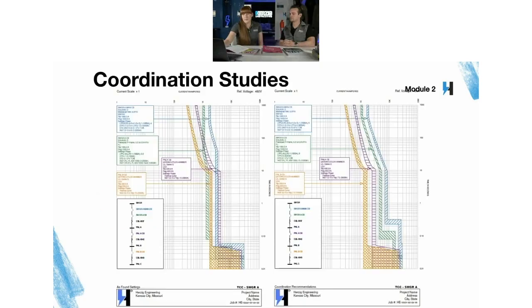Okay. All right, so here's that example that I was talking about. So the TCC curve, or time current characteristic curve, of each protective device is plotted on this log chart. TCC. Yes. And basically, the super high level, going-to-make-engineers-mad version of talking about this, we've color coded it and we don't want the colors to overlap. And we want them to be in a specific order. Now, again, that's a super simplified version of saying that, but just for your sake of looking at these, the one on the left is very clearly not adequate because we want the blue to be furthest to the right and not overlapping with anything, because otherwise you're going to have a much higher outage area than necessary. And we want the orange furthest to the left and not overlapping with anything, so that its direct feeds are the only thing that it's going to need to worry about operating. So left to right, much improved coordination.